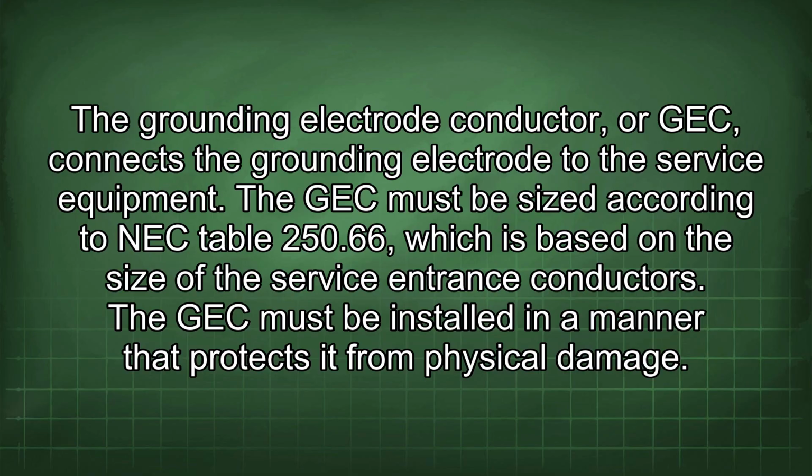The GEC must be sized according to NEC table 250.66, which is based on the size of the service entrance conductors. The GEC must be installed in a manner that protects it from physical damage.